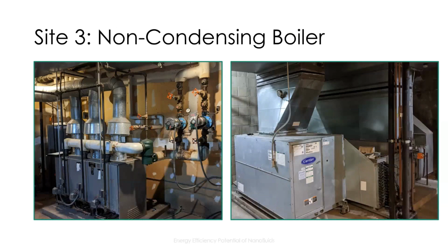The third site is a non-condensing boiler. This system serves a single air handler that has heating coils in the zones. We also had full automation access for this site, and we pulled the data intermittently before it was overridden. This setup included a gas meter that we were able to data log, as well as airflow monitoring through each of the terminal heating coils. So we calculated an air side load for each of the coils, and then compared that to the natural gas input to estimate the efficiency.